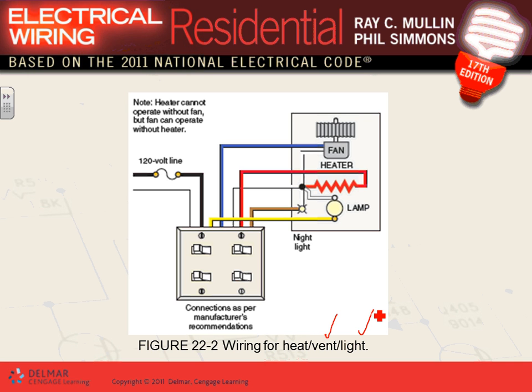If it has heat, if it also provides heat, can you guys see that little heating element right here? Now you have a completely different story here. Then you have to provide a 20 amp circuit dedicated to feed the whole combo. So what this guy does is very simple. I don't know if you have seen it or not. There are switches, switch 1, 2, 3, 4. This will switch the fan, turn the fan on, turn the heat on, turn the main lamp on, turn the night light on. So they have a night light.